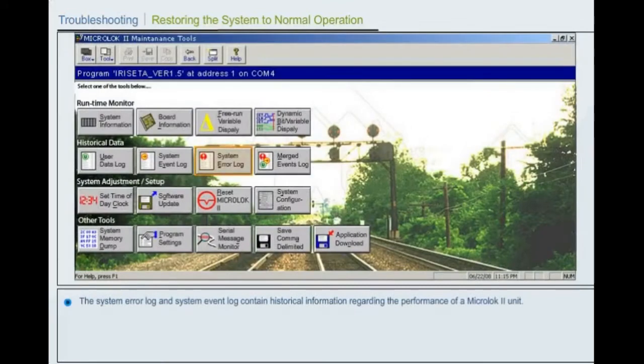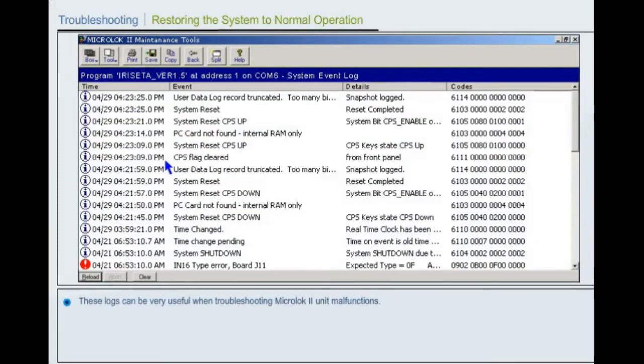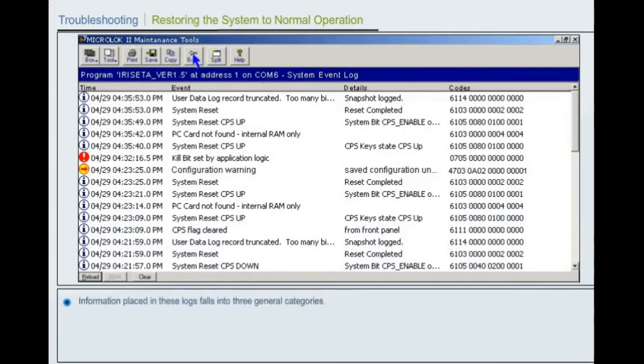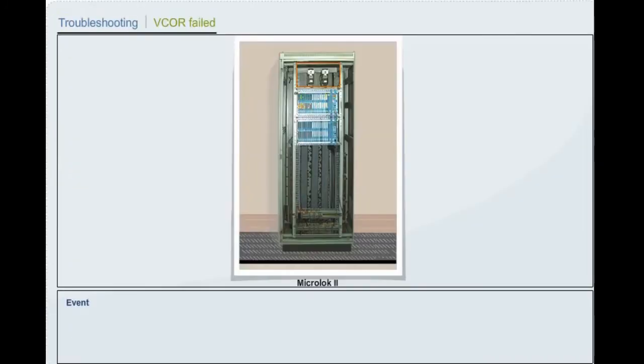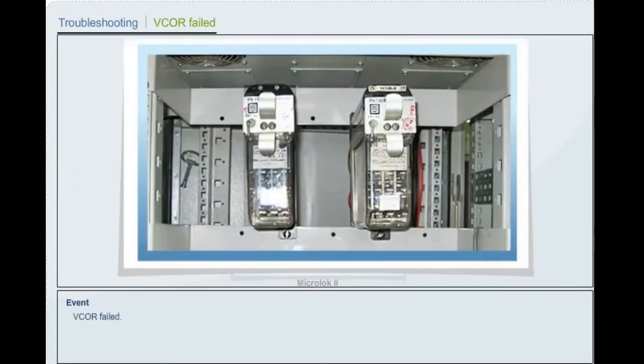Troubleshooting. Restoring the system to normal operation. The system error log and system event log contain historical information regarding the performance of a Microlok 2 unit. These logs can be very useful when troubleshooting Microlok 2 unit malfunctions. Information placed in these logs falls into 3 general categories: critical errors, warnings, events. Event: vital cutoff relay failed.